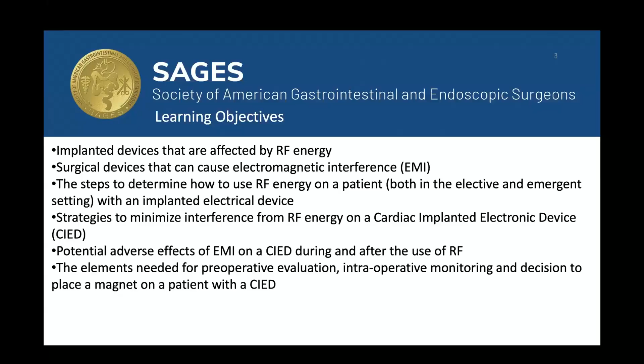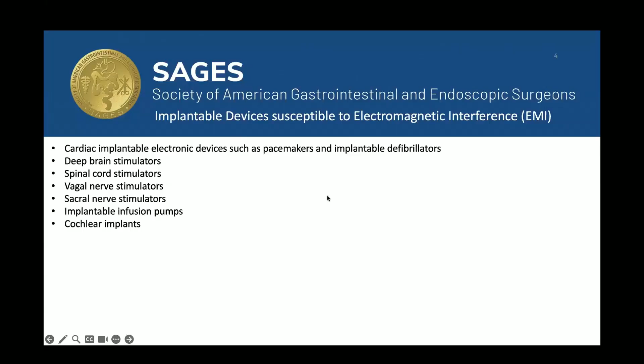In terms of implantable devices, they're susceptible to electromagnetic interference. The number one thing we look at is the cardiac implantable devices, which are two main types, pacemakers and defibrillators, or sometimes they're in combination. But it's always worth remembering that things like deep brain stimulators, spinal cord stimulators, vagal nerve stimulators, sacral nerve stimulators, implantable infusion pumps, and cochlear implants can all be affected. These are less common and less relevant in emergency settings.